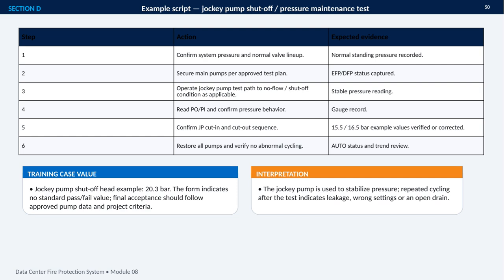Next, I operate the jockey pump test path to a no-flow or shut-off condition where applicable. I record the stable pressure reading, read the pressure outlet and pressure indicator, and document the gauge behavior. The next step is confirming the jockey pump cut-in and cut-out sequence. The example values shown are 15.5 and 16.5 bar, but these must be verified or corrected against the approved criteria.